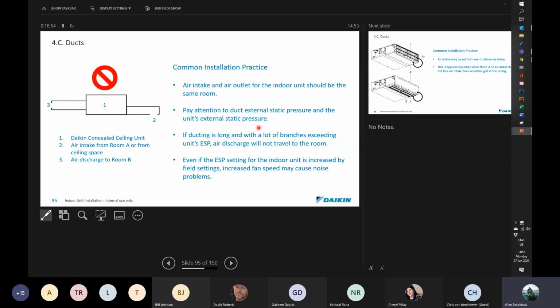On our medium static units, you may need to adjust this. You've got quite a range, and on our high static, you've got an ability to adjust as well on the smaller ones. On the FX DQs, those are low static, you've only got 2 options, and those units are generally designed for bulkhead applications. So don't go add long runs of ducting onto low static units.